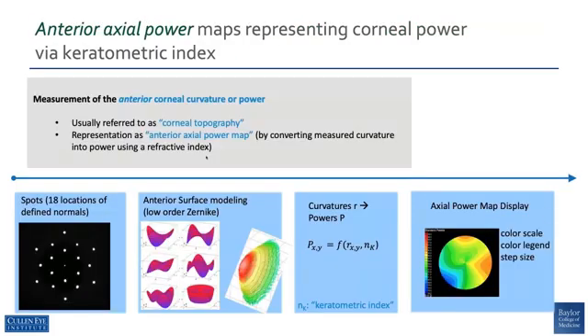Anterior axial power maps representing corneal power are calculated using the keratometric index to give an estimation of total corneal power. You start with the LEDs, they undergo a modeling process and computations, and an axial power map is displayed from the LEDs.